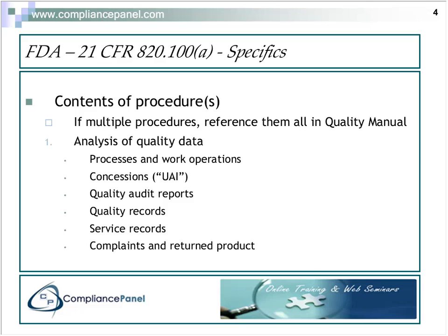CAPA can originate from many different areas, and specifically in the regulation here, it lists quite a few of those areas. What I've done in the past is my quality manual talks about my CAPA practices very generally, that we implement CAPA programs, but it pulls together the procedures in response to which CAPA can be introduced. For example, my complaint handling procedure, my in-process quality data analysis procedure, my service procedure, design control, things like that. So I do have multiple procedures, and I reference them in the quality manual.